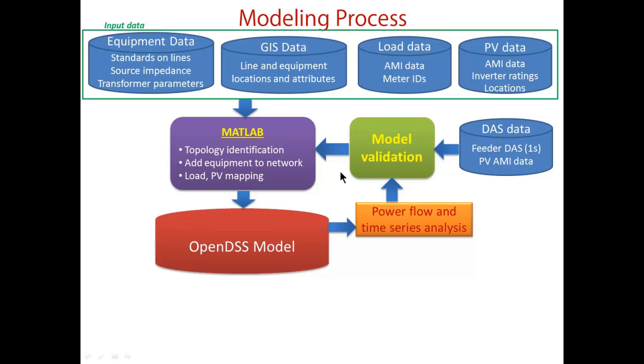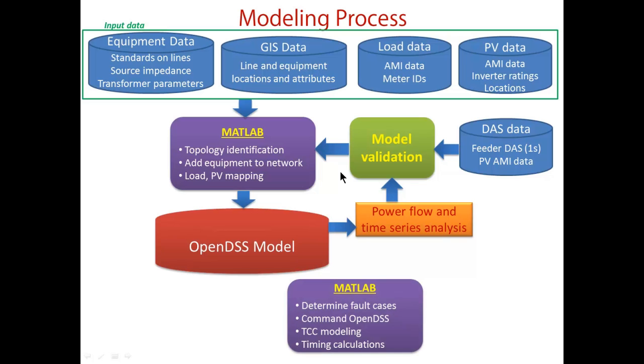So through this validation, we have a very accurate feeder model on which we can have a high level of confidence. So once we have this, then we can use this model for the protection analysis. Once again, MATLAB is the main analysis engine that we use for the protection study as well. So in this part, the MATLAB determines all the fault cases that we need to run for a specific coordination analysis, say fuse to recloser.